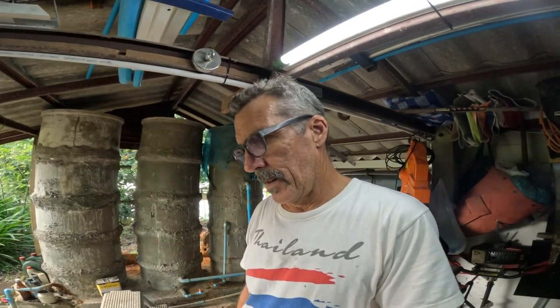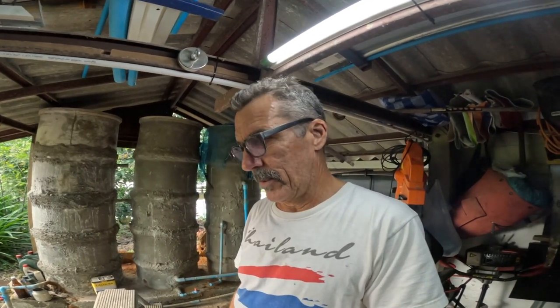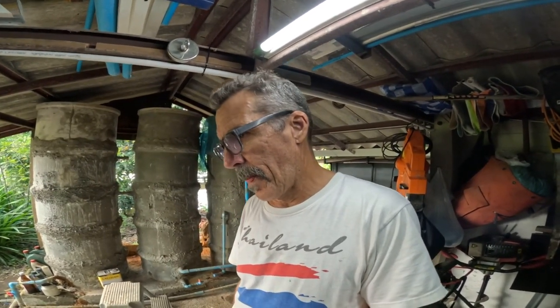I tested it with my amperage, voltage meter, and it's just too much. I'm pulling too many amps from that 16 amp fuse when I have everything going. So I'm going to have to call the electrician guy and see if he can run a line for me.